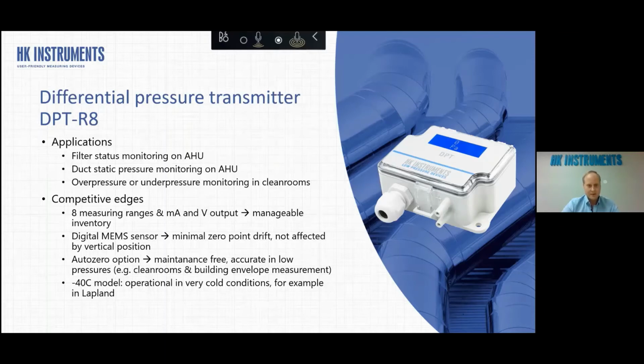And what we have in this is 8 different measuring ranges. So basically you can find the most commonly used ranges in the same unit, so you don't have to have a big inventory for different applications. Instead, you can use basically 1 or 2 different models. And this has both milliamp and voltage output that you can choose with the jumper settings. And the sensor technology we are using is a digital MEMS sensor. And we have seen that the zero-point drifting, which used to be typical for this kind of sensor technology, doesn't exist that much anymore. We are talking about maybe ±2 Pascal drifting over 1 year, but not bigger than that.